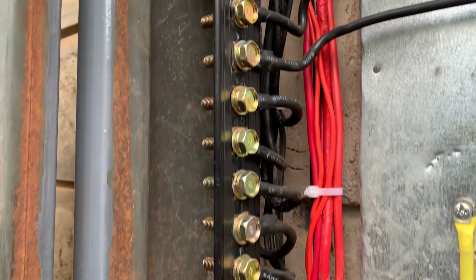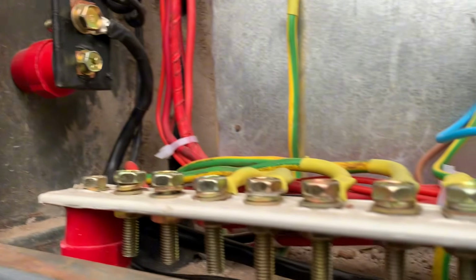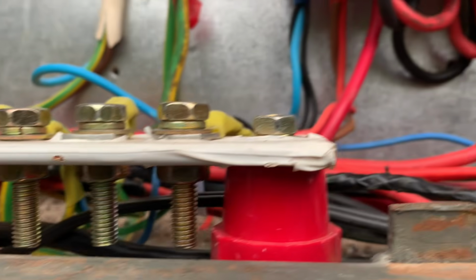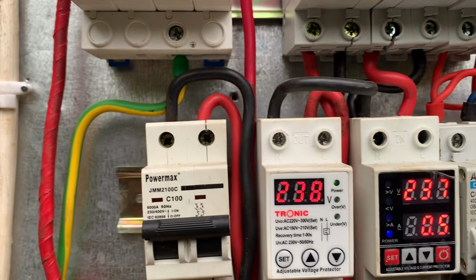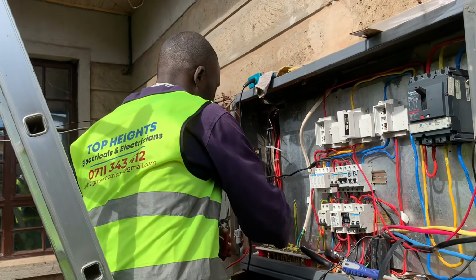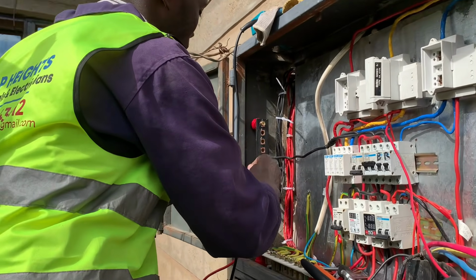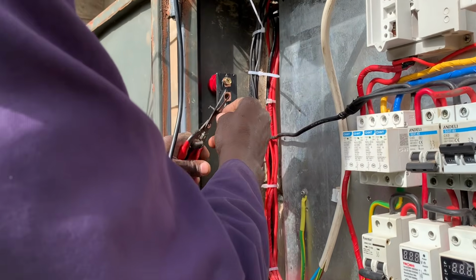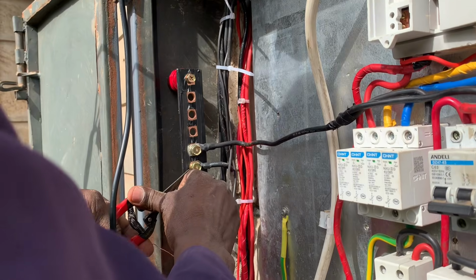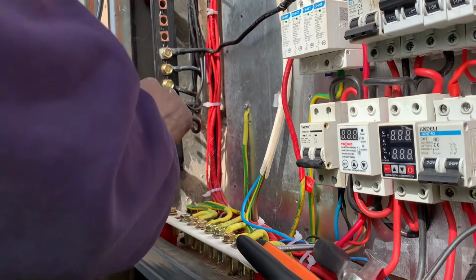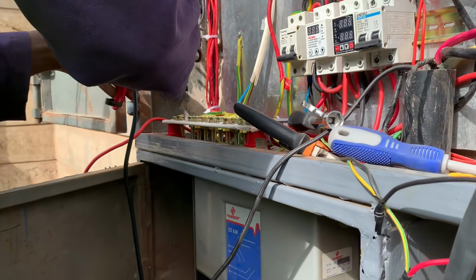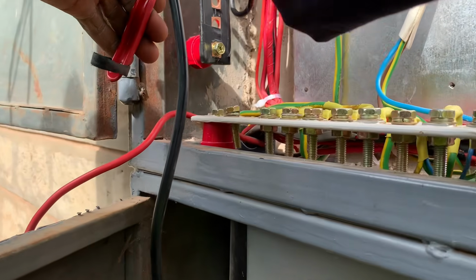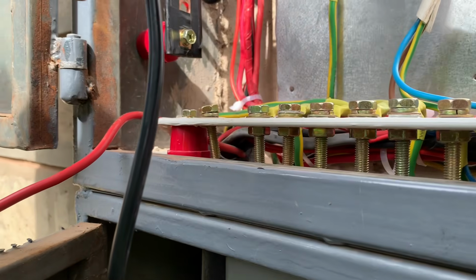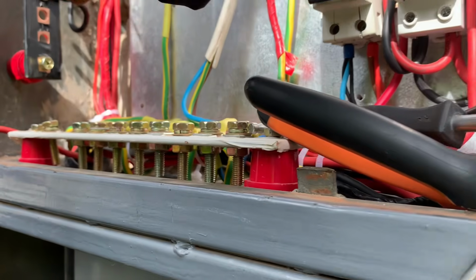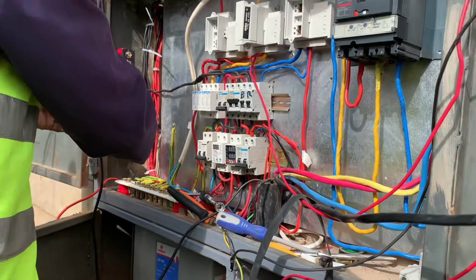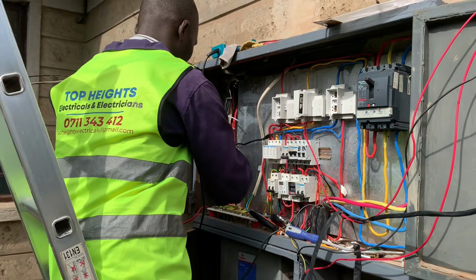Phase and neutral must give you the same values, especially here where we expect 230 volts AC. That is what we need to be getting, and that has to be consistent with the other phases. If there are variations, they can only be very, very small. But again, you must ensure that the quality of the electrical work that has been done is definitely above par.